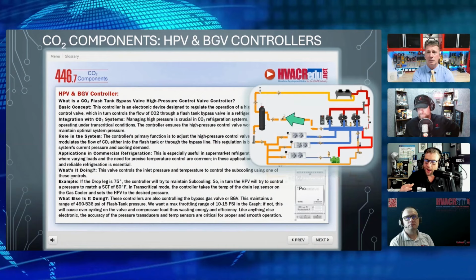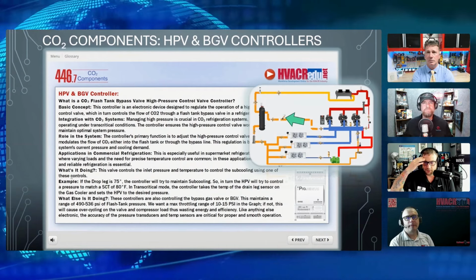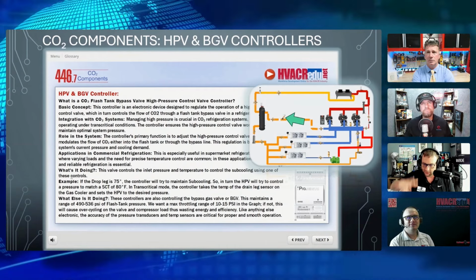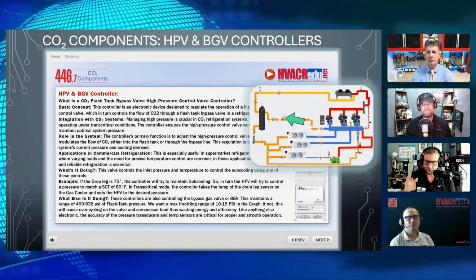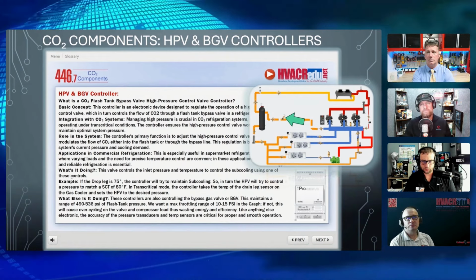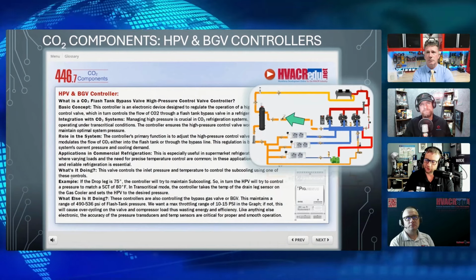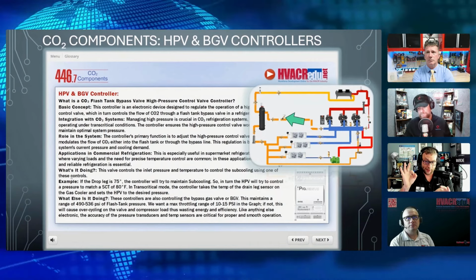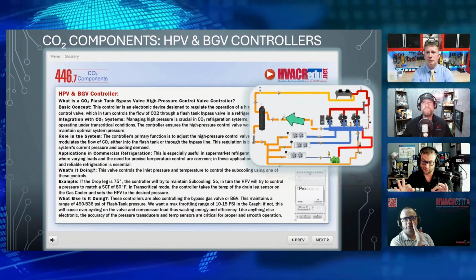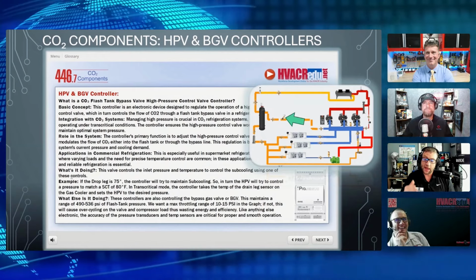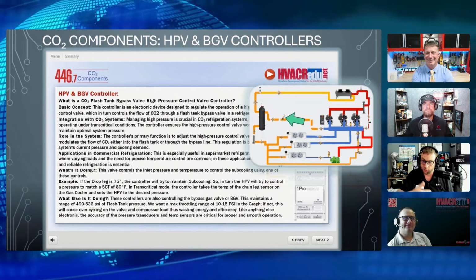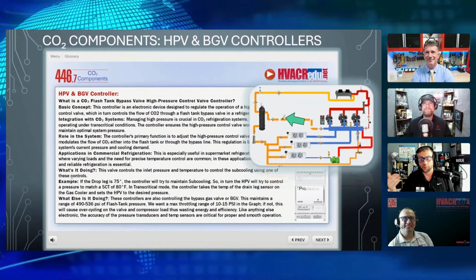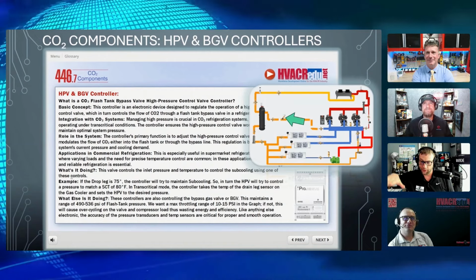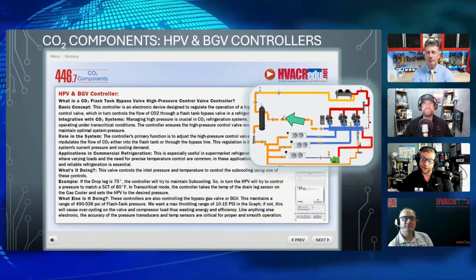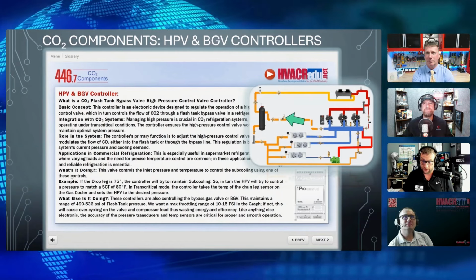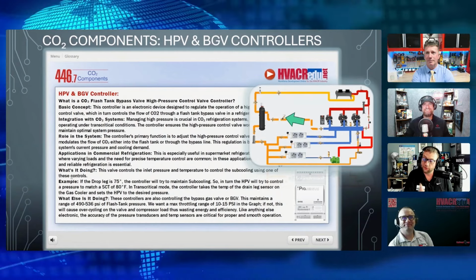I had a real hard time wrapping my head around this when I first started learning this. And I was like, man, this doesn't make any sense. Because how do we have subcooling and then it disappears? And I tried to explain a flash tank is almost like a recovery cylinder. You know how sometimes on the recovery cylinder you have the blue that's labeled liquid and the red that's labeled vapor, like they're backwards? Yeah, the ones that they messed up. Yeah. And if you accidentally, like I have, pulled off of what I thought was the liquid, you end up pulling off the vapor. And what happens? We drop the pressure within the vessel, it drops down to the saturated, and then it gets all freezy cold. Like I broke the refrigerant. Now it's cold. What happened? That's how a flash tank works.